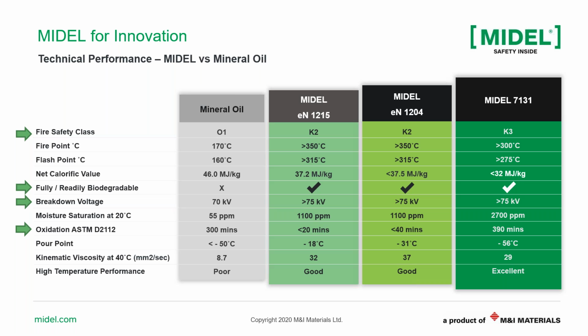And finally, I wanted here also to highlight the oxidation aspect of these fluids. Mineral oil is known to be oxidation stable, and also synthetic ester, MIDEL 7131 here, is also oxidation stable. But natural esters, as I said earlier, can only be used in sealed units, hermetically sealed units, or with rubber bag, where we can guarantee there's no exposure of the liquid with air. Otherwise, you would have oxidation. Oxidation can lead to high acid value and to higher viscosity, and then higher temperatures, and then could be failure. So I only touched base on 4 aspects here: the fire, the biodegradability, breakdown voltage AC, and the oxidation.